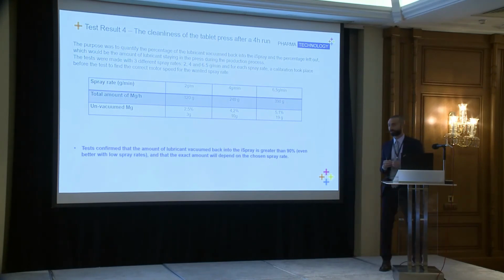The last point for this test was the production test: how can I compare the machine with something that after 2 hours I have to stop and clean? Is that clean enough? So we checked the unvacuumed magnesium stearate. The majority of the magnesium stearate is vacuumed back. What stays in the punches and die is really nothing. With a spray rate of 2 grams per minute, I have a total of 120 grams sprayed, and the unvacuumed amount is only 3 grams. So 3 grams out of 120 is what is left in your press.